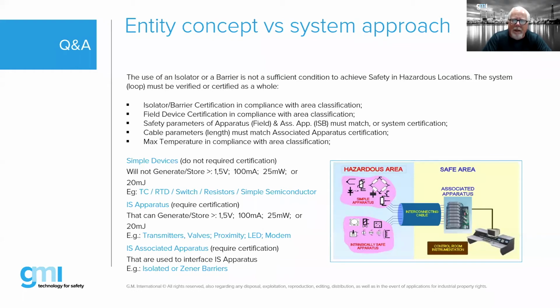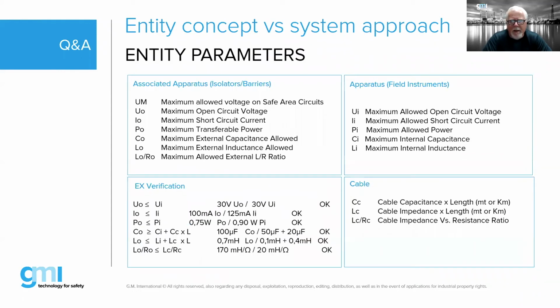Well, the reason why we need that information is that we have to take into account the entities of the various devices. So our associated apparatus, our cable, our field devices, we need to take all of that into consideration. So basically, is the barrier in compliance with the area classification? Is the field device compliant? Are the safety parameters matched, right? Or must they be lower than or equal to, or what have you. And then the cable parameters. This is the one thing people forget about, but cable will store energy, right?